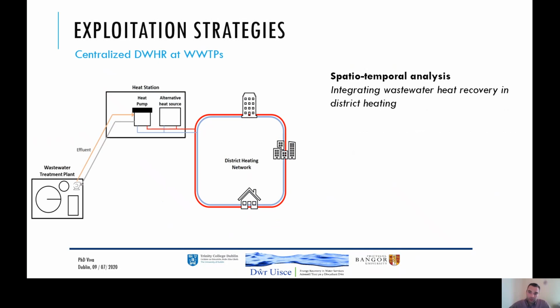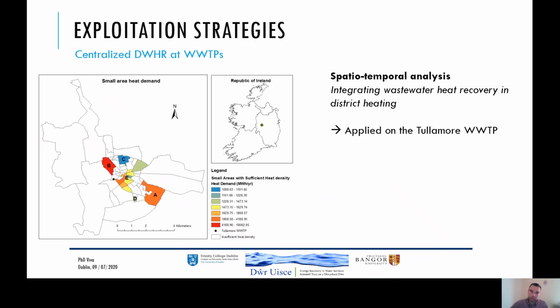And we developed a spatio-temporal analysis for integrating wastewater heat recovery in district heating, where we used the effluent of the wastewater treatment plant, so clean water, as a heat source for a heat pump, which then delivers its heat to a district heating network. And we applied our analysis on the Tullamore wastewater treatment plant, which you can see here on the black dot. And the spatial component of our analysis showed 5 different zones where the heat demand density was of such a nature that it could justify district heating.